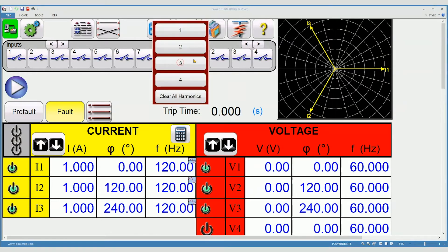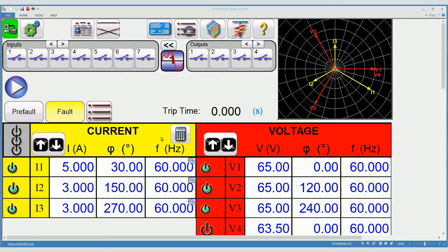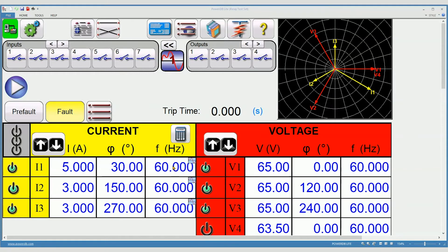When you return to fundamental frequency and you perform a manual ramp, the amplitude of the harmonic frequency remains fixed so that you can now ramp through the harmonic restraint area.